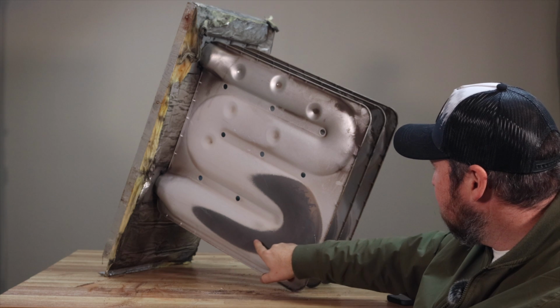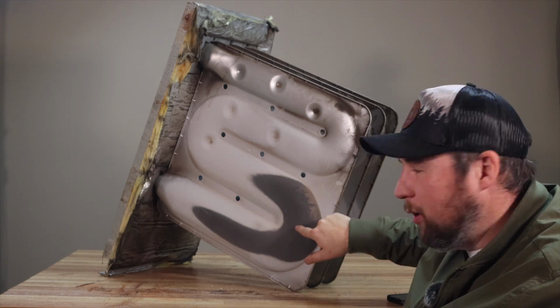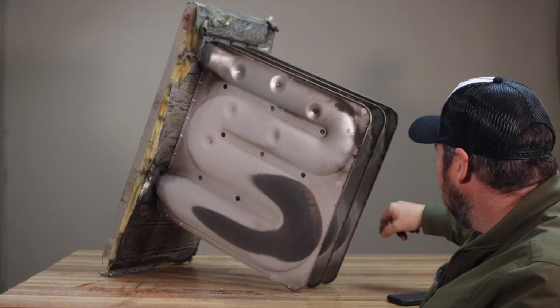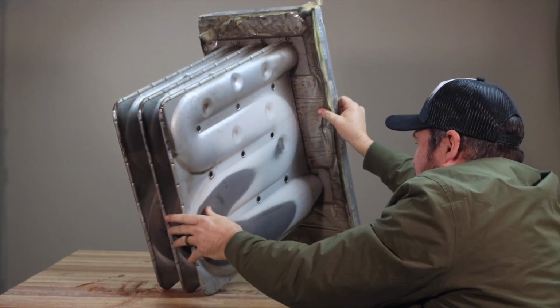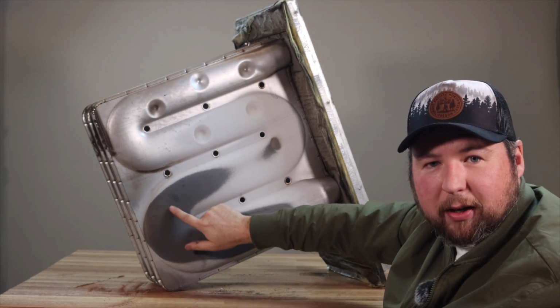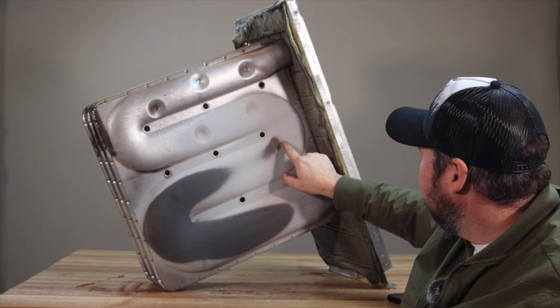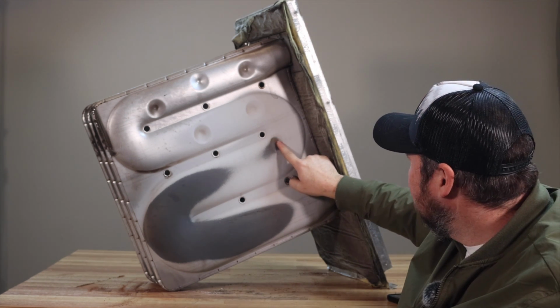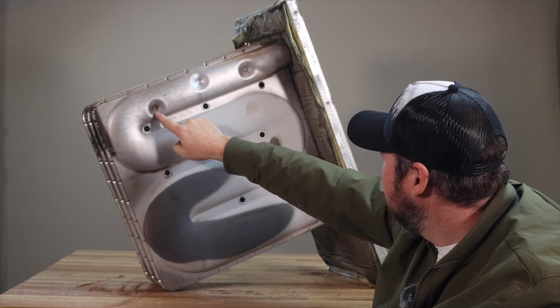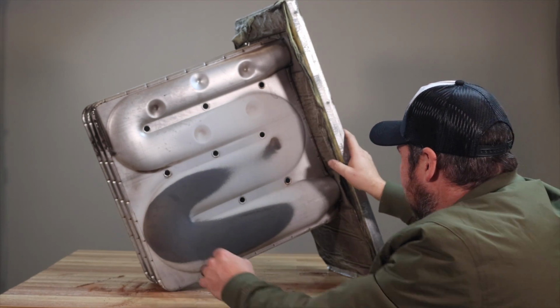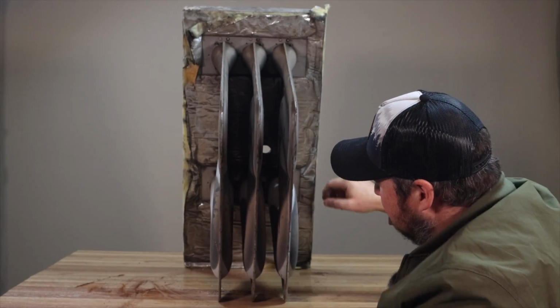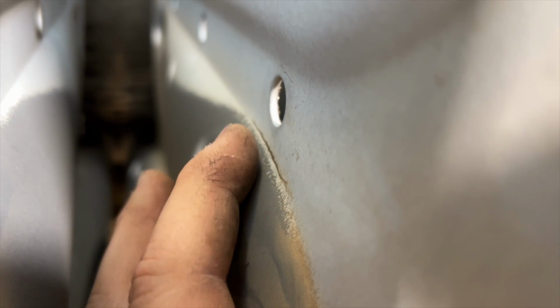And like I said, usually it's going to be on that first turn, and you'll see it sometimes on the other turns. Now if we look on the other side, we can see right here on the turn, and then we have a hot spot right here. And there is a little divot right here, and that's just to kind of maximize heat transfer. You can see that they have a bunch of them. But this was a hot spot, right? Now if we look in the middle, we can see our cracks. So you can see here, we have a crack right there forming, right on the edge of that. And you can see it's completely toasted. It's all black, temperature stress like crazy.